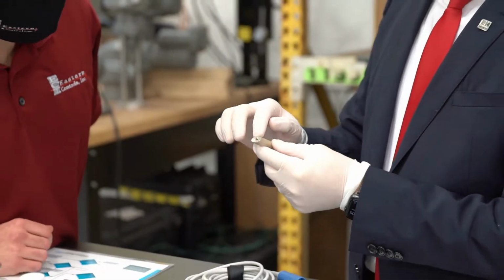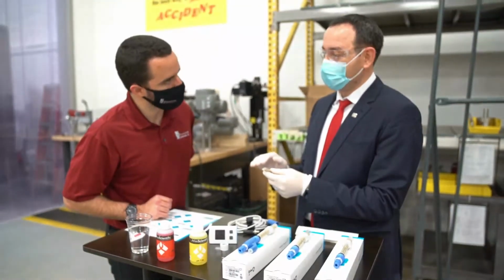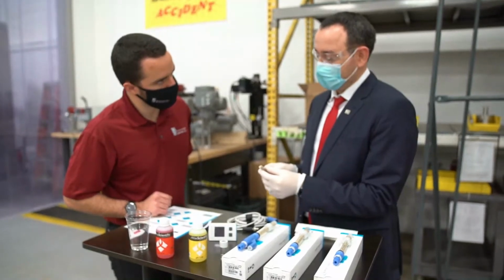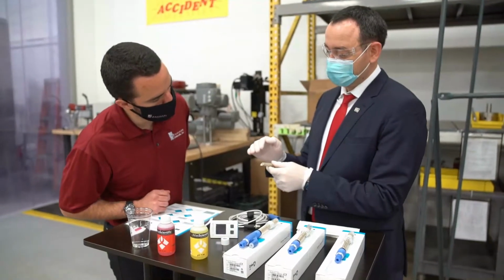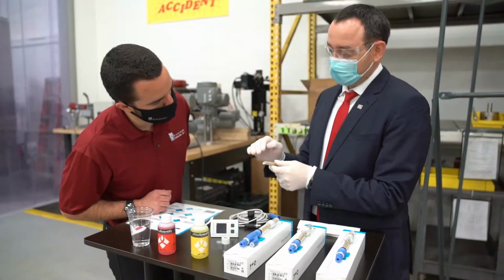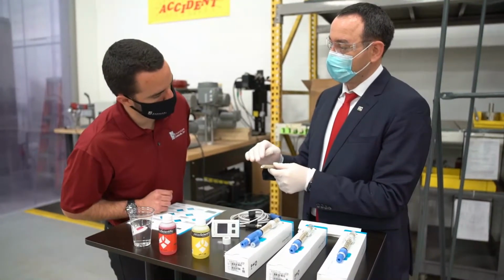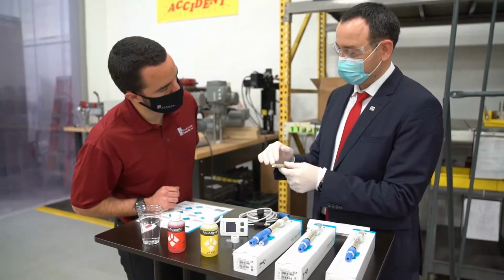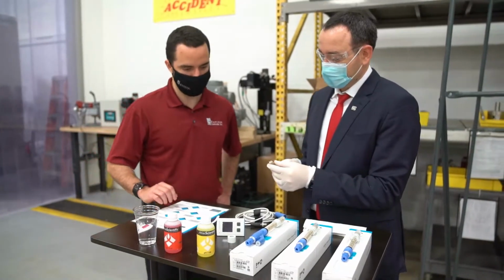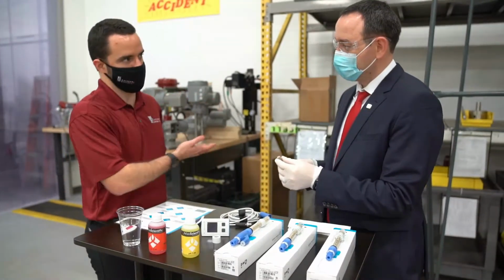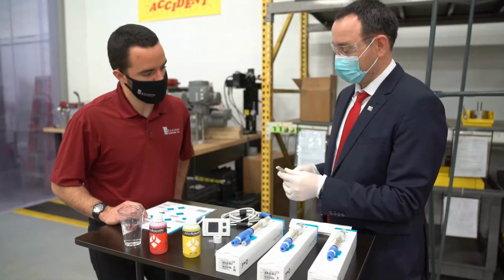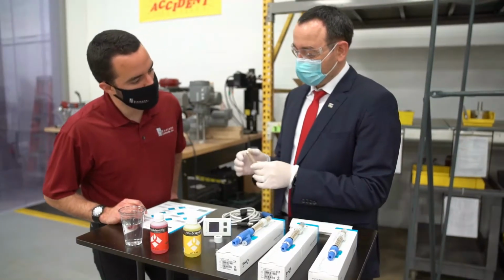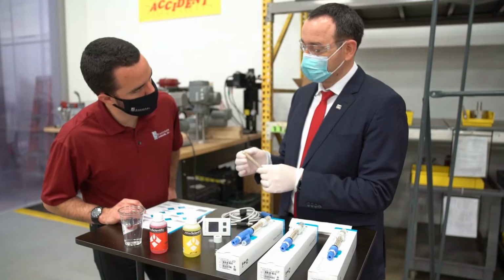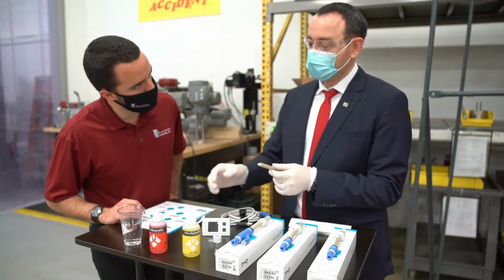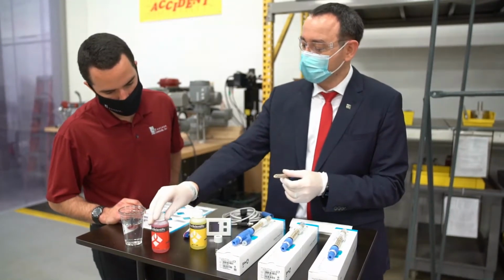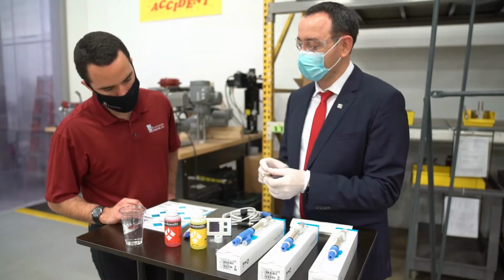So for completely cleaning, there is no universal cleaner. We need to find the suitable cleaning solution that dissolves the buildup. That makes sense, which we can probably have already in stock for the buildup. Correct. So once we ensure the probe is clean, then we verify the reading with the pH buffer 4 and 7.